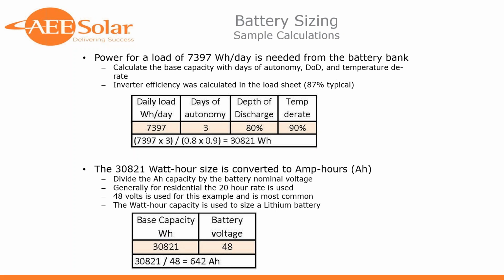You know, for a lead acid battery, you would need to change that to amp hours, which is sort of the opposite of the formula that I gave earlier, where you're taking the watt hours and dividing it by the voltage, and it gives you the amp hours. In a lithium battery, you can just start with that watt hour size and just go with that. You know, change it to kilowatt hours. And of course, don't forget that your inverter is not 100% efficient, so you have to put that in the calculation also, which I am not showing here.